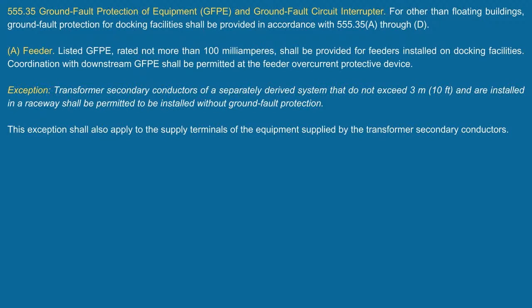So it's not just receptacles that require GFCI protection. That would include lighting outlets as well. So if I have luminaires on my dock, on my boatyard facility, I've got to have GFCI protection for those as well. If I have hardwired equipment, remember hardwired equipment terminates at an outlet where the hardwired equipment meets the premises wiring, that's the outlet. So it's not just GFCI protection for receptacles, it's GFCI protection for just about everything that's on that marina or boatyard. Oh yeah, everything, man, just everything.